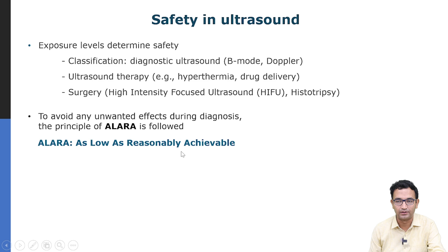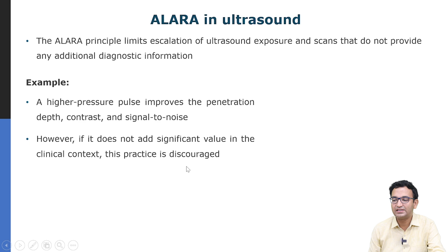In general, if you use a higher pressure pulse, it will improve the penetration depth, the contrast and the signal to noise ratio. However, we are making this ultrasound image for clinical use and not for cosmetic use. So, there is a limit to how much diagnostic information is contained in the image on the basis of these parameters. Beyond a certain signal to noise ratio, you may not need to further enhance it by increasing the pressure. So, the idea here is to keep the signal to noise ratio enough to make your diagnostic call, and beyond that it does not serve a purpose and it increases the risk of adverse bioeffects. So, there are cases where it may not add significant value in the clinical context, and therefore, increasing the exposure levels is discouraged. So, I will give you an example.